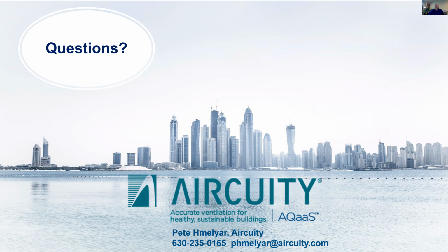Thank you. There was another question as well. What is the maximum sampling interval permitted per space when utilizing a common sensor suite? Very good. We have done testing that shows the maximum time to be able to react, and the maximum time we ever allow is 15 minutes.